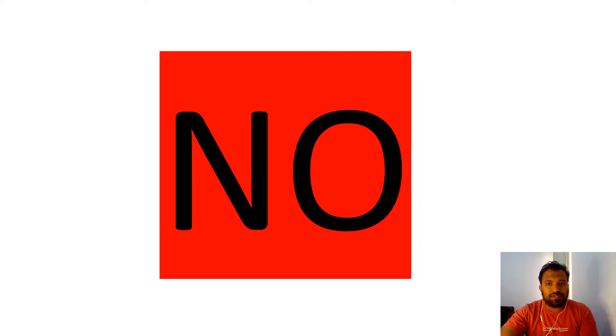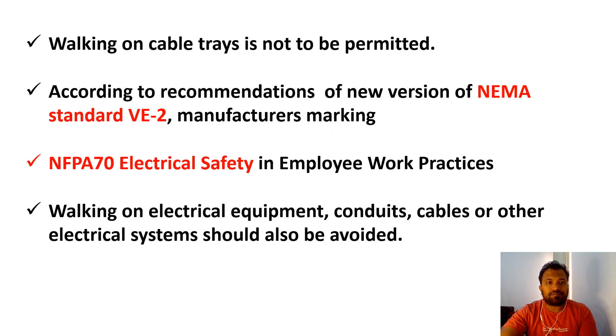Is there any standard against those things? Walking on cable trays is not permitted. According to NEMA standard VE-2 as well as NFPA 70 electrical safety standards, it is clearly indicated that people should not walk on cable trays.